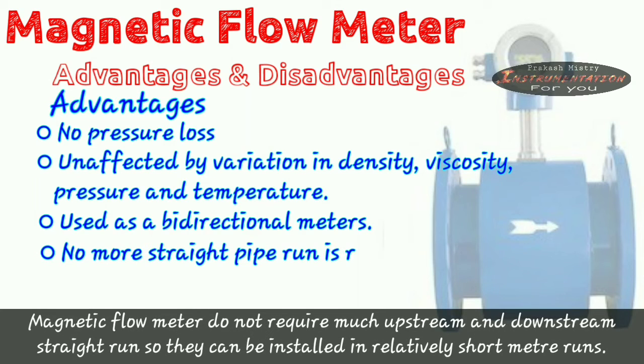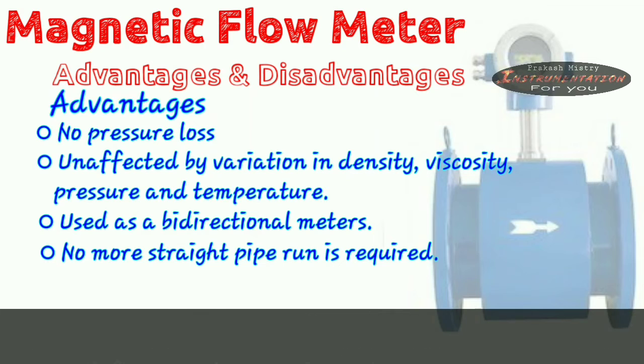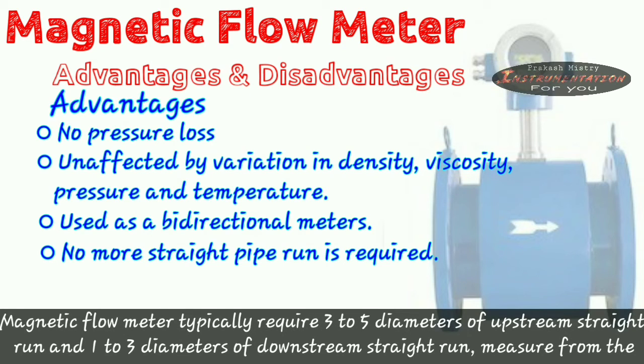Magnetic flow meters do not require much upstream and downstream straight run, so they can be installed in relatively short meter runs. Magnetic flow meter typically requires 3 to 5 diameters of upstream straight run and 1 to 3 diameters of downstream straight run.